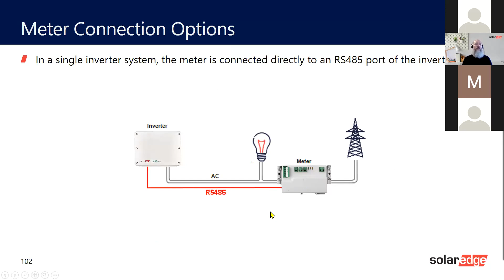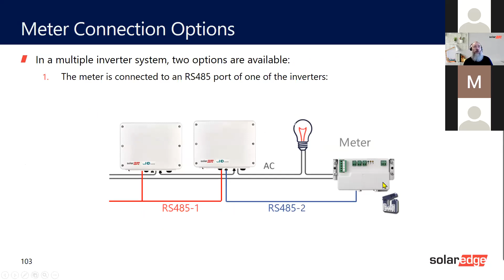Both RS485 are supported, and remember you must do the dip switches for end of line for both of them. So for the leader, you must do the end of line dip switch, and the very last follower, you must do the dip switch, and the same for here. This one has dip switches, you'll see them later on. The inverter has a dip switch as well, and so does the meter.